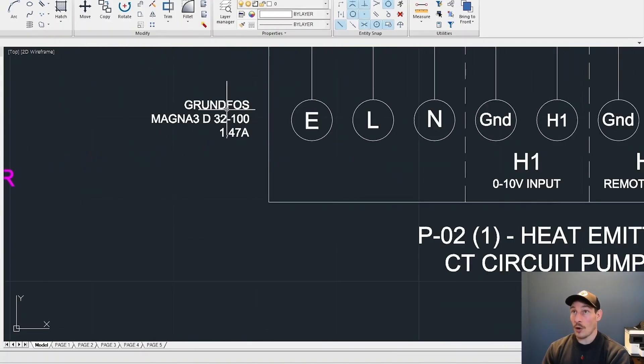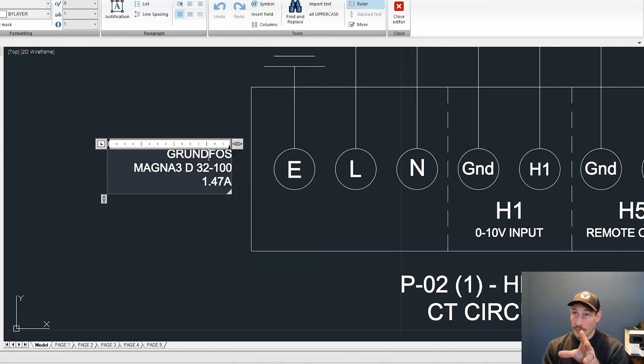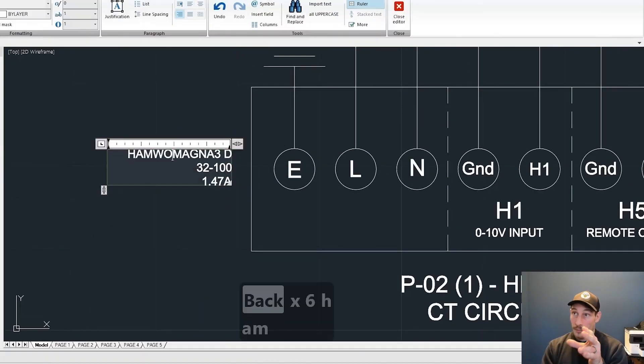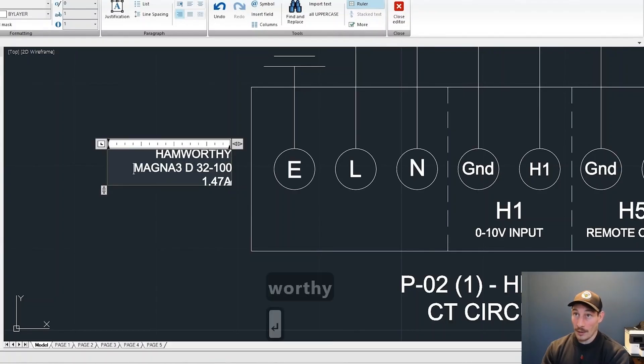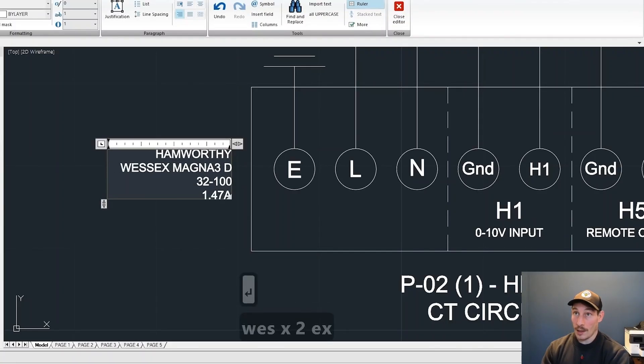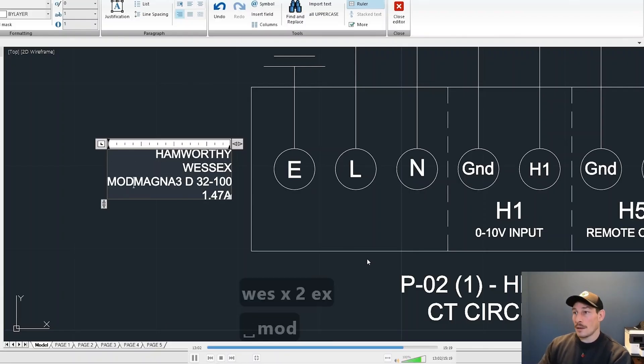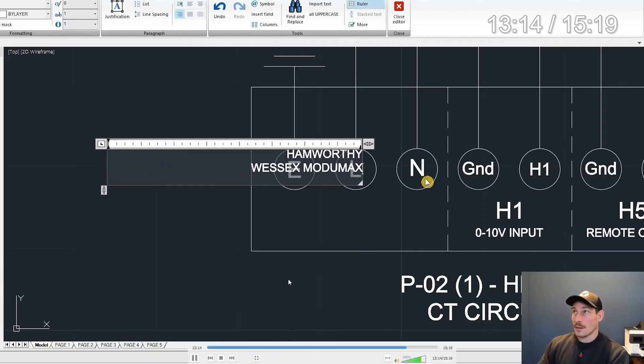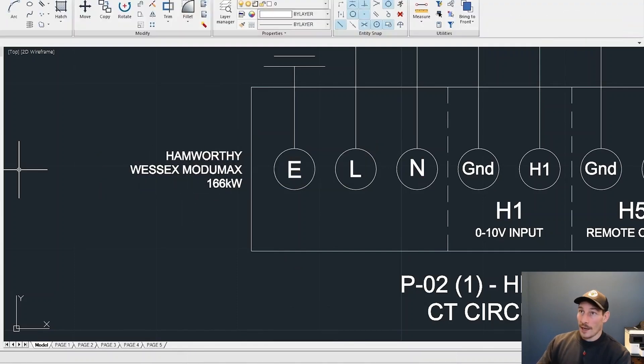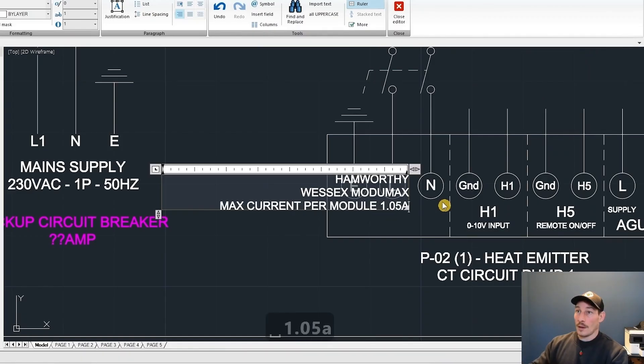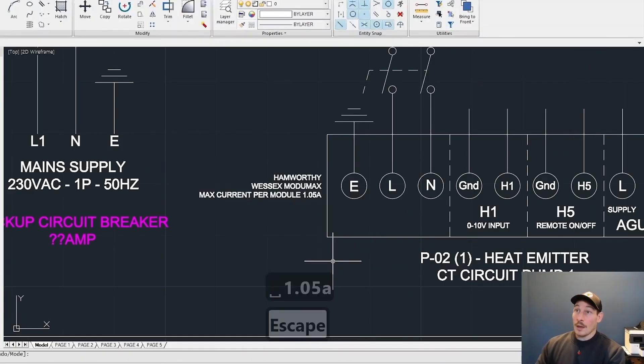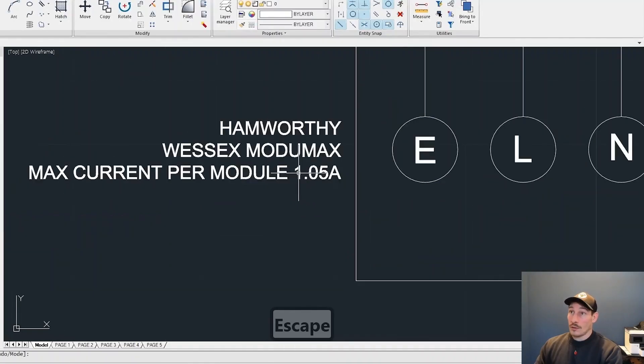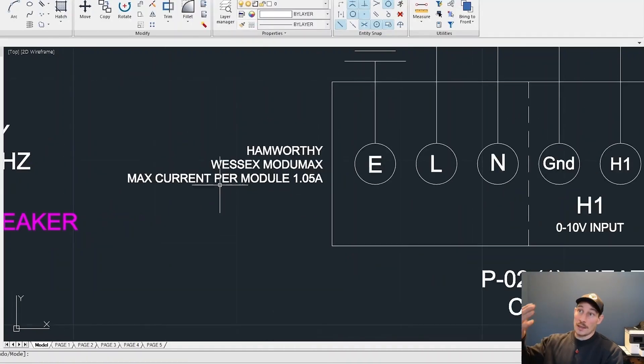You can see I'm just copying the text again from that Grundfos pump block that I'd already created, and now I'm just renaming it to a Wessex boiler. All the details of the components are written here. We want to know the max current draw as well so we can size breakers appropriately further up and cables as well.